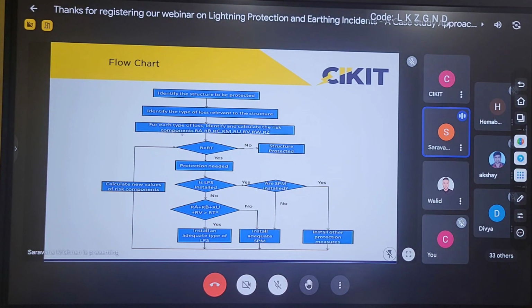But it does not mean that if the value of risk is lesser than RT, lightning won't strike the structure. Even if the lightning strikes, the damage will be lower. That is what it means. So if the risk is lesser than RT, we cannot consider that there won't be any lightning strikes on my building. Even if the lightning strikes, the damage will be much lower and manageable.